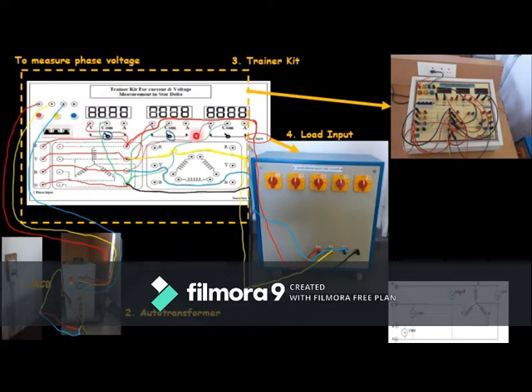In all three different meters, we have to put the switch towards the left position, where we have the marking of V. So I have to move the switch towards the V direction. That is what you have to consider in case of a star connected system. In case of a delta connected system, you position the switch towards the right side where it measures current. The phase current and line current in a star connected system will be the same, so we are not measuring current here. We are measuring the line voltage as well as the phase voltage, and we are going to determine the relationship between the line and phase voltage.